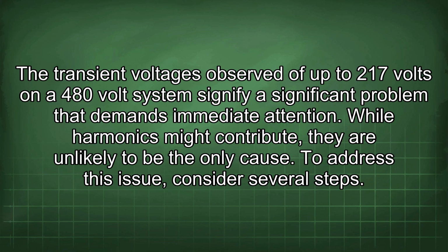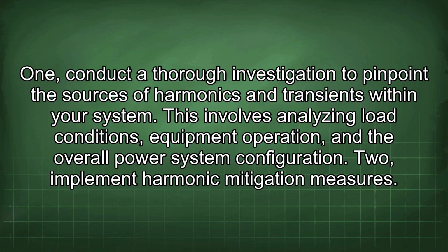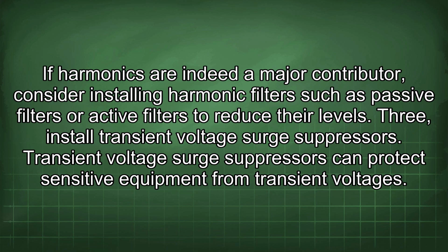To address this issue, consider several steps. 1. Conduct a thorough investigation to pinpoint the sources of harmonics and transients within your system. This involves analyzing load conditions, equipment operation, and the overall power system configuration. 2. Implement harmonic mitigation measures. If harmonics are indeed a major contributor, consider installing harmonic filters such as passive filters or active filters to reduce their levels. 3. Install transient voltage surge suppressors.